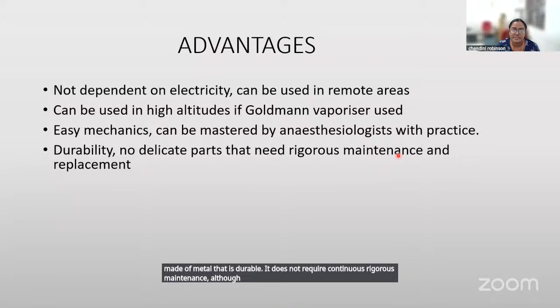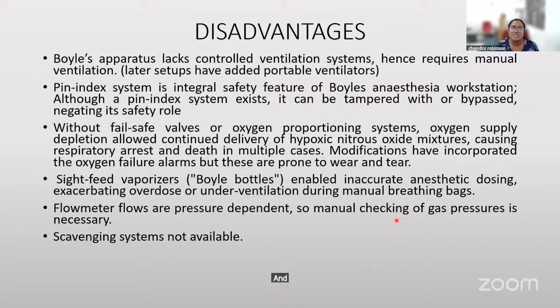The disadvantages list is long, and the Boyle's apparatus lacks a controlled ventilation system. So we require manual ventilation unless we can set up a portable ventilator along with it. There are no fail-safe valves, there are no oxygen proportioning systems. Sometimes there may be a possibility of delivery of a hypoxic gas mixture, so constant vigilance is required. Flow meter flows are pressure dependent, so manual checking of gases is constantly necessary, and there is no scavenging system available with the Boyle's apparatus.